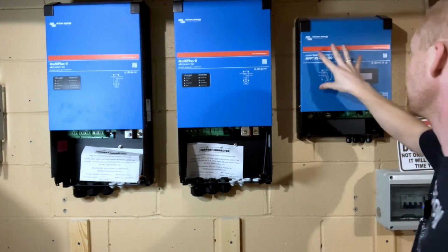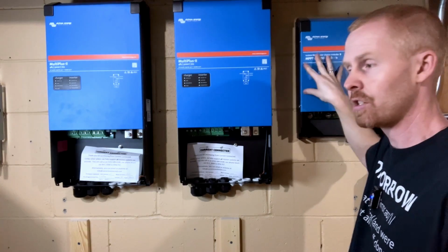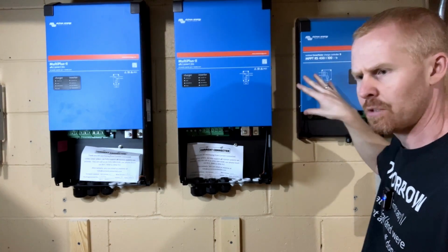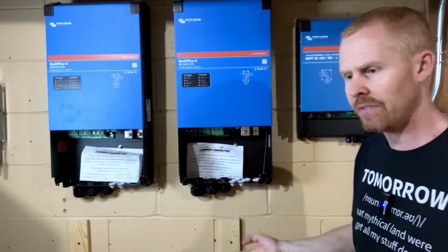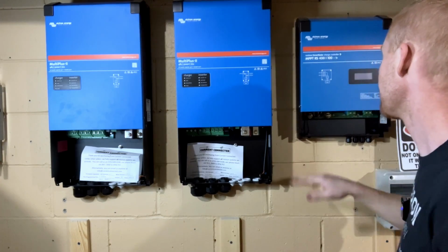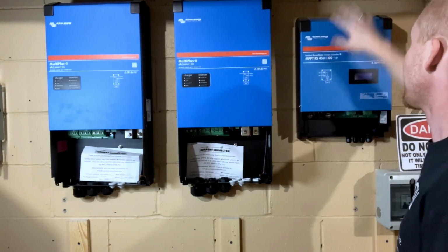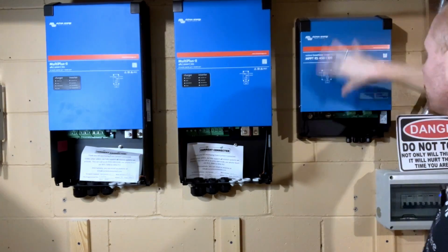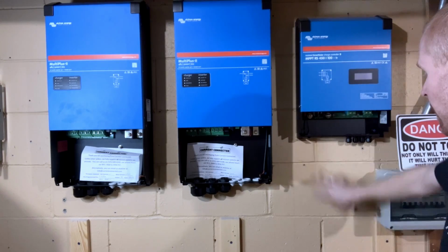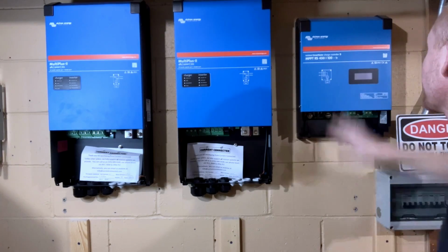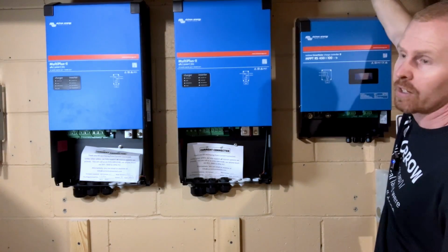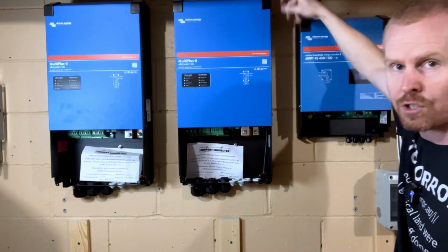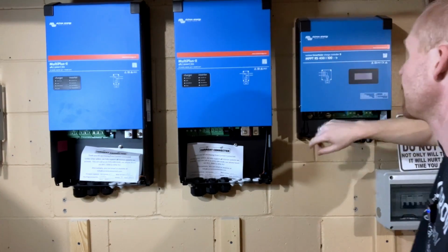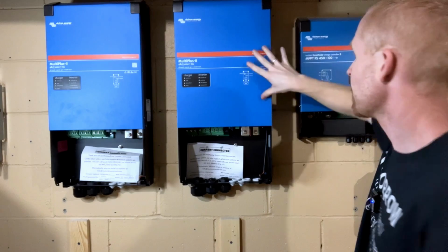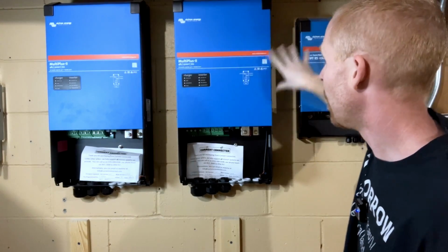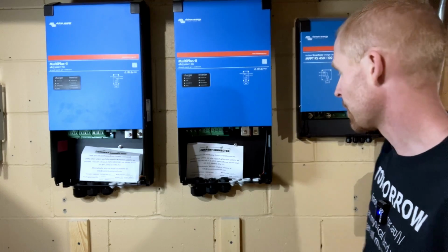Then you've got your charge controller, which I think I mentioned before, is not part of the 10 kVA kit. You get that separately. But you've got to have 12 inches of vertical clearance on the charge controller, and 12 inches of clearance down here. I've got just enough clearance up behind this trunk, which you might be able to see in the camera. You've got to have 4 inches of clearance on either side all the way around for the inverters.